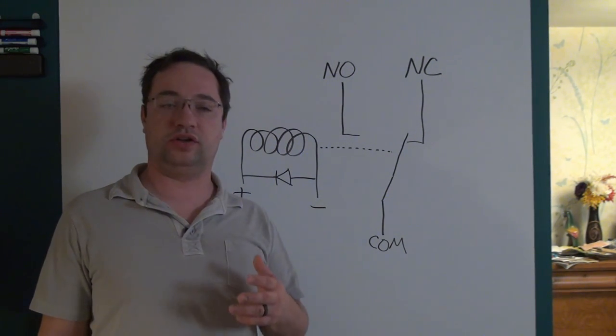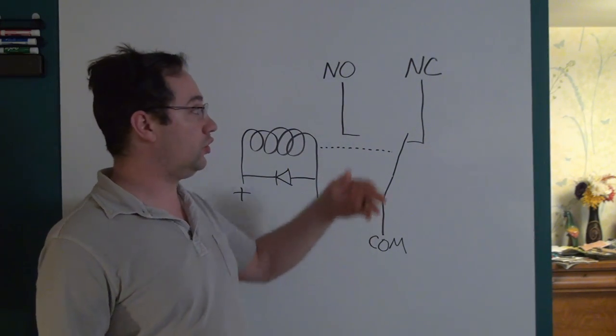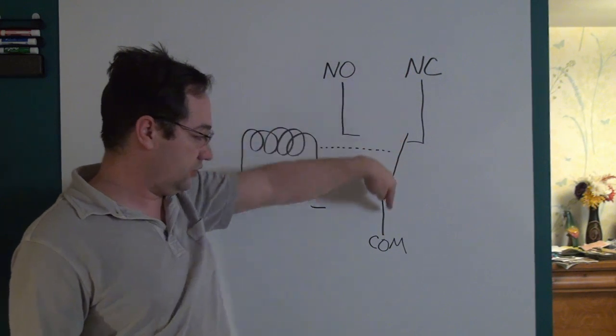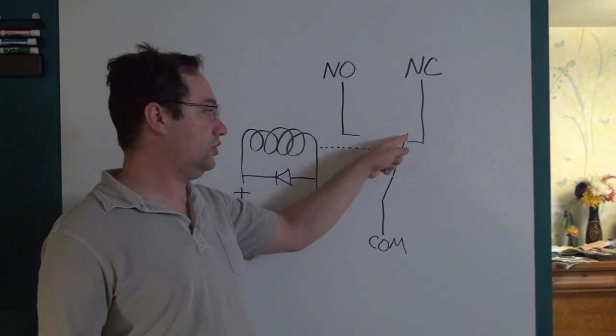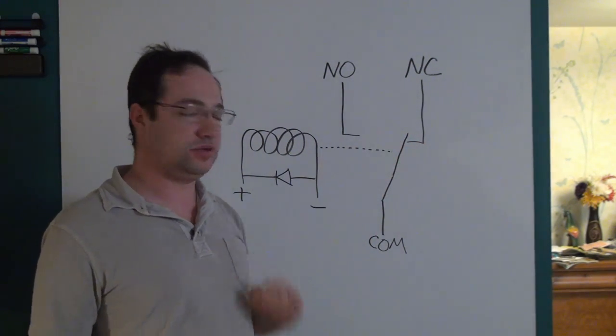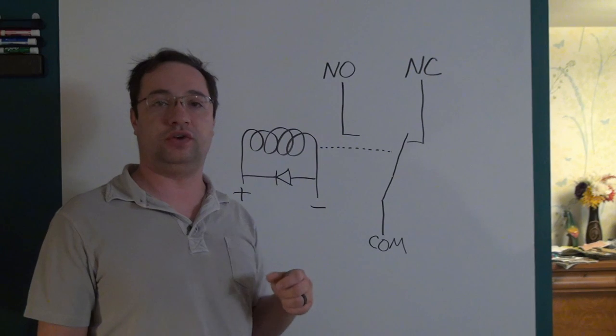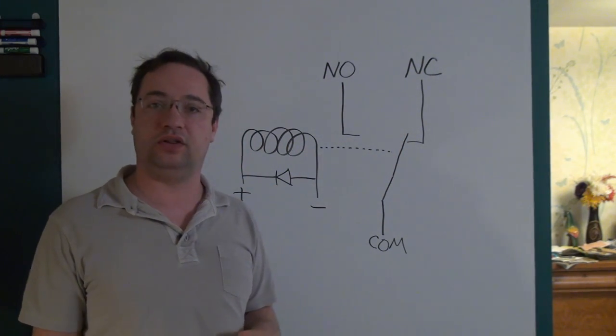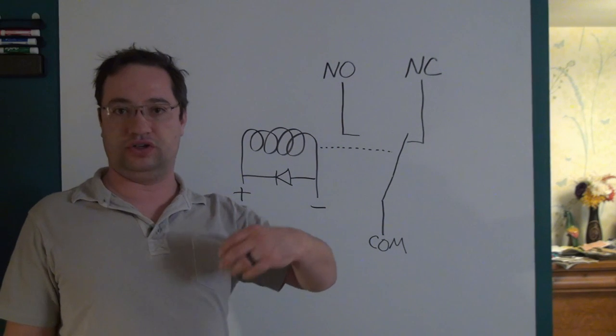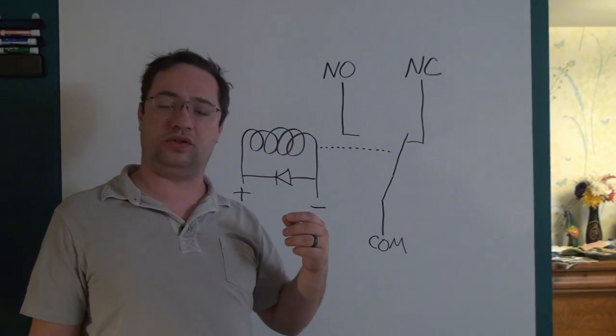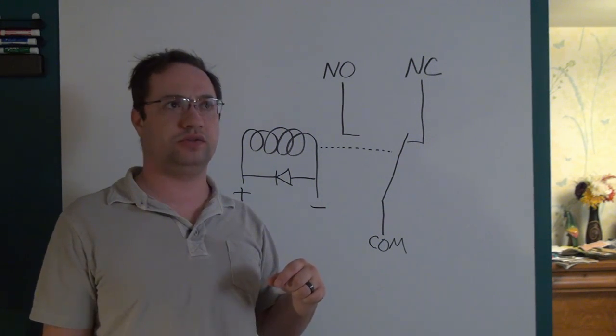With AC current, it's easier to deal with because whenever the contact switches — for example, if you have something on the normally closed contact and current is flowing — as the contact begins to move and the contacts separate, an arc will form, and this is pretty much unavoidable. But with AC, that arc will quench quickly because the current goes to zero 120 times a second, so in the time the relay contact starts to move and an arc forms, the arc will quench.